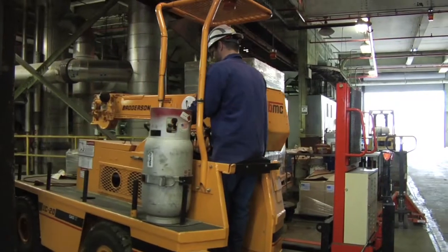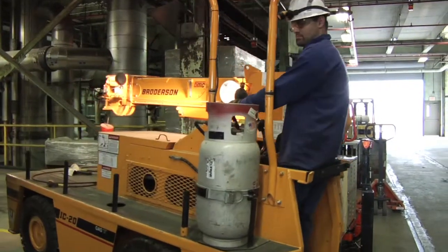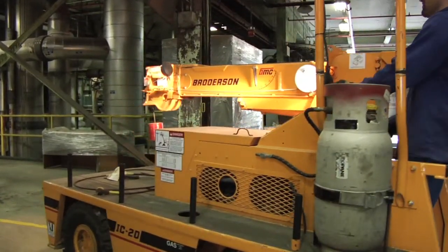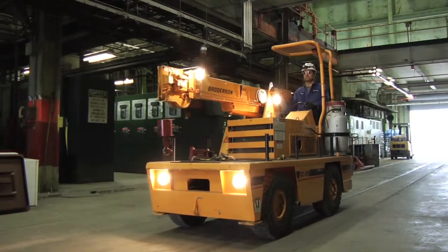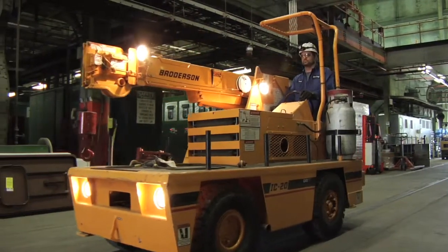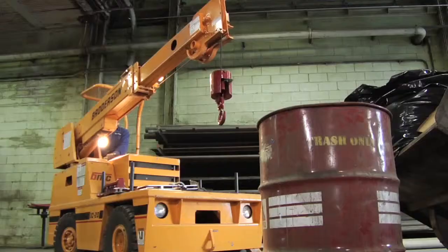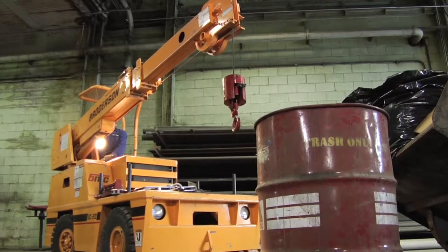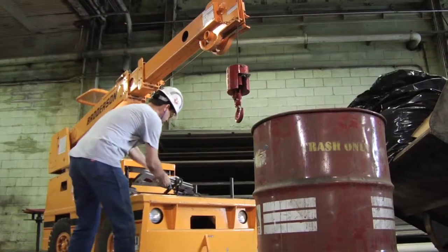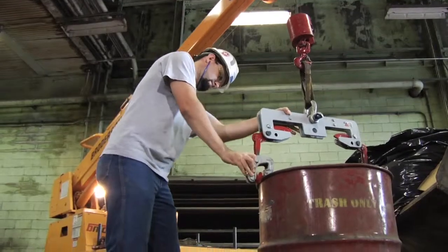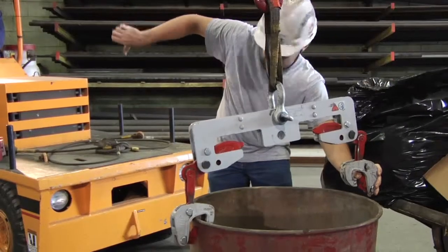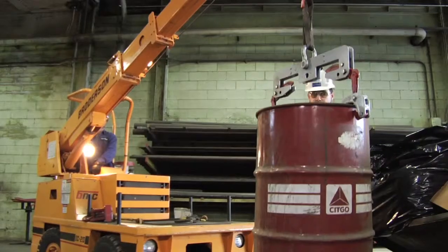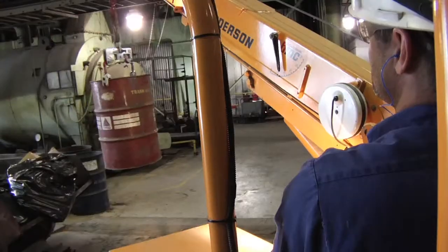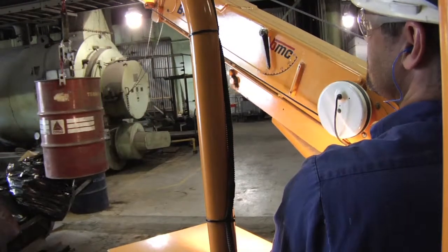If you're using a mobile crane, all OSHA regulations for operating the crane must be followed. Critical lift plans must be developed by qualified personnel and submitted for review to Hoosier Energy. Only trained personnel can operate mobile cranes, and all parties involved in a critical lift must be briefed during a meeting prior to operation. All rigging equipment requires a damage inspection before each use. Taglines should be used unless they create a safety hazard.